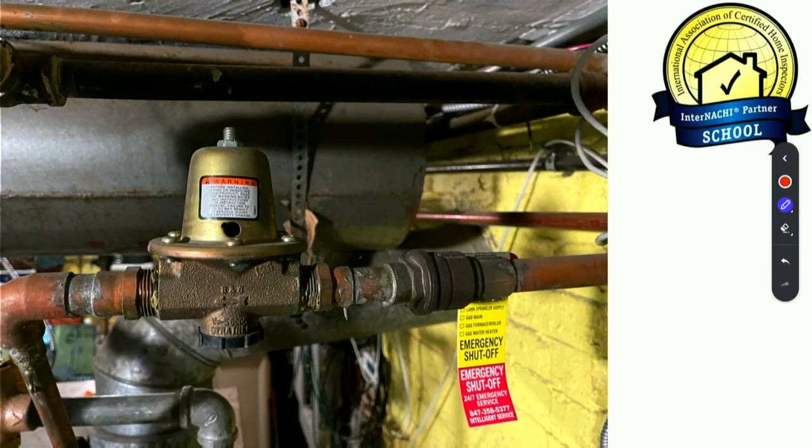One thing that's kind of important, and I really don't think it would work without this, is this little arrow. Can you guys see that okay? That arrow is also a one-way backflow prevention valve. And what that does is create a closed system, because once water gets into the heating side, past that arrow, everything on this side is closed. So we're going to have pressure relief valves. We're going to have expansion tanks. We're going to need that once things get hotter, because the water's going to want to expand, and we need to be able to absorb that with air. Exactly.